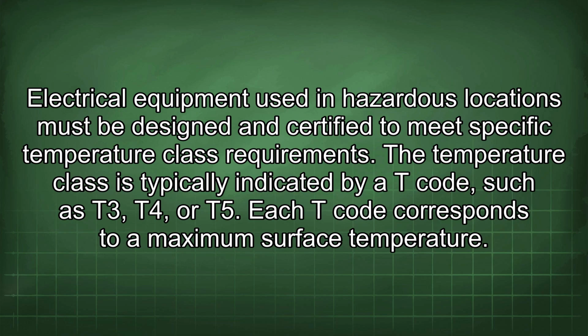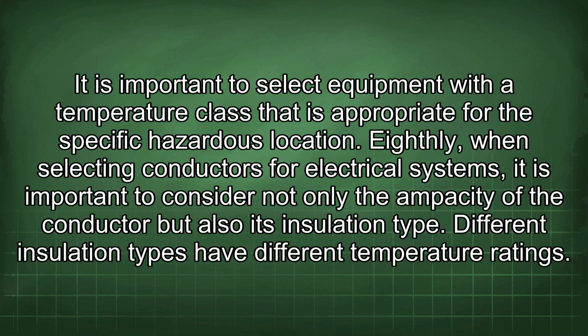Electrical equipment used in hazardous locations must be designed and certified to meet specific temperature class requirements. The temperature class is typically indicated by a T-code, such as T3, T4, or T5. Each T-code corresponds to a maximum surface temperature. It is important to select equipment with a temperature class that is appropriate for the specific hazardous location.